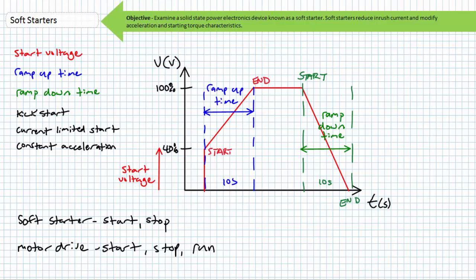This is to suggest that most motor drives also have adjustable start voltages, ramp up, and ramp down times to govern the starting and stopping characteristics of motors. This lecture, therefore, serves as an introduction to motor drives. As we'll learn in later lectures, motor drives vary applied frequency and voltage during the run stage to govern the output speed and torque of the driven load using advanced closed and open loop control.